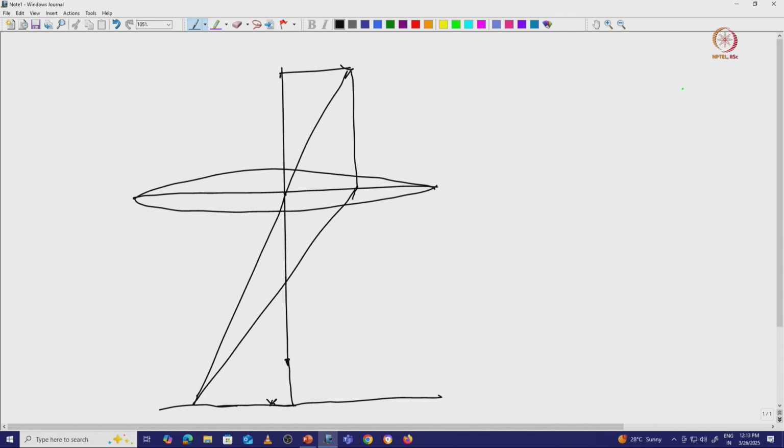Now, when we are using this magnetic field, there will be a crossover point here, and this is, we can say, the focus point in this particular magnetic field. Another possibility: if I have a little bit stronger magnetic field, stronger magnetic field means it pushes this electron beam towards this direction, and you can see there is a merge and it will give us an image somewhere here.